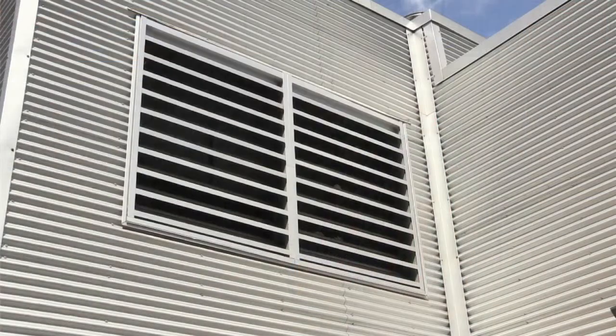Besides all of that, do I have exhaust fans, supply fans? I can hear the cooling towers up on the roof. That's a good thing. They obviously should be running. But do I have other exhaust fans or intakes? Are they blocked? Do I see intake louvers? I've got some louvers right here. Are they plugged up? Am I near debris, trees, leaves, grass?